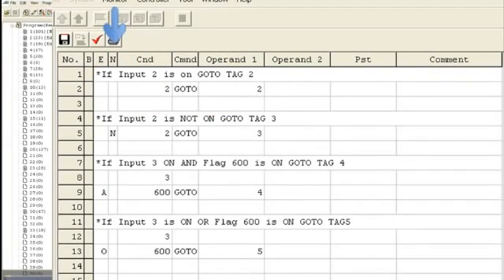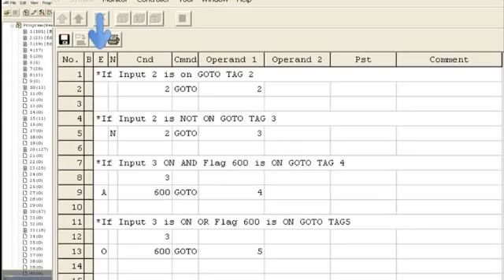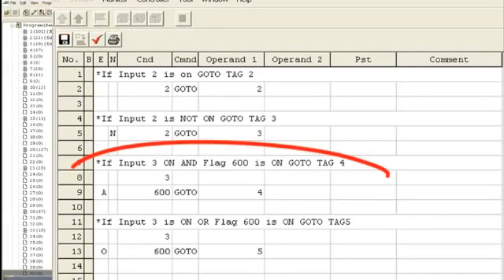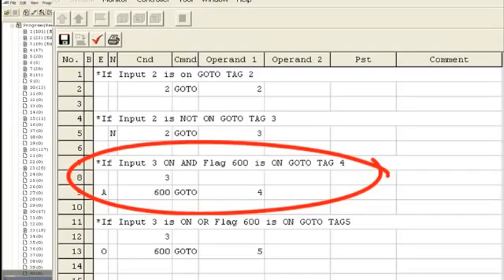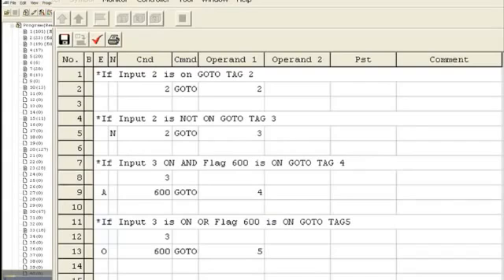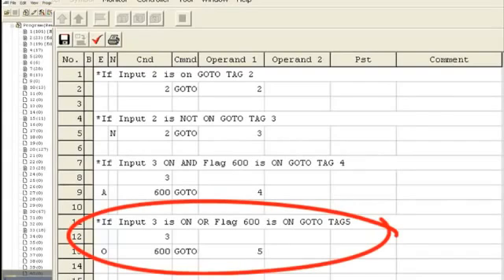The N column is used for a NOT condition. If INPUT 2 is NOT ON, execute the command. The E column is the expansion column. An A can be put in the expansion column for an AND command. If INPUT 3 is ON AND flag 600 is ON, execute the command. An O can be placed in the expansion column to be used as an OR statement. If INPUT 3 is ON or flag 600 is ON, execute the command.